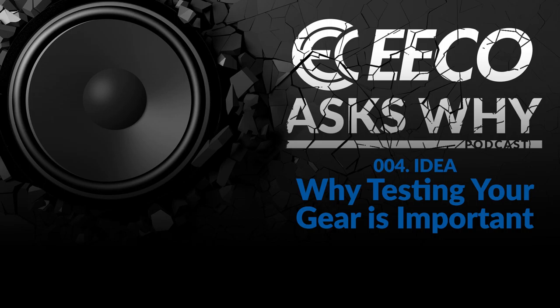Yeah, absolutely. So as you're trying to build an electrical system from scratch, it's a little bit easier to hit some of these topics, because you're basing a lot of your analysis on good information. So you know the age of the equipment, you know what equipment you have, what breakers you have, what fuses you have, what cables you're going to use. So with new construction, going through short circuit and coordination studies, arc flash studies, load flow studies, and harmonics analysis, all of that is pretty simple, it's pretty reliable.